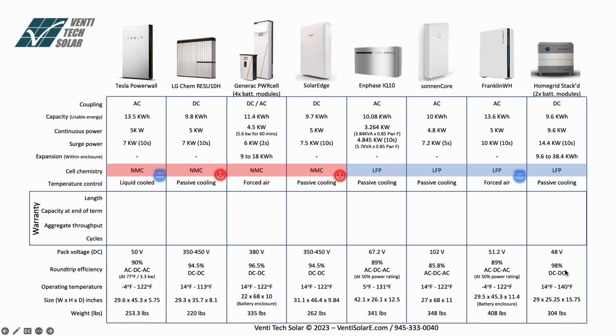I think that number is a little high. I was expecting something like 95 or something like that. So that could be depending on the way they do the testing, or there is not much DC to DC conversion because the cells are already 48 volts. So the conversion from low voltage DC to high voltage DC will come out at the inverter level. So they're not accounting for that.